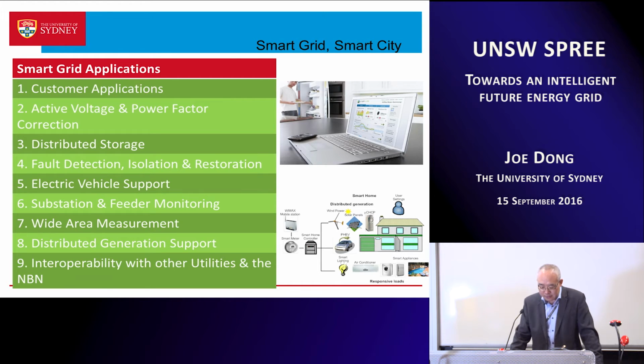Fault detection, isolation, and restoration - if you've ever experienced a blackout at home, you know you need to call Ausgrid or whatever network company. If they receive a number of calls, they'll send an engineer to identify the location and the problem. Under fault detection, isolation, and restoration, given measurement devices, the operator will know immediately what's going on and where the fault is. Then 90 or 95% of faults can be recovered within 5 minutes. They can then send an engineer, depending on the distance, to that specific fault location, which can be fixed in 20 minutes, 1 hour, or 2 hours.